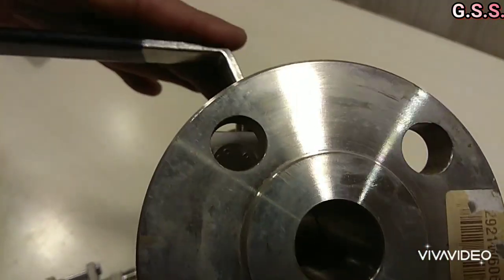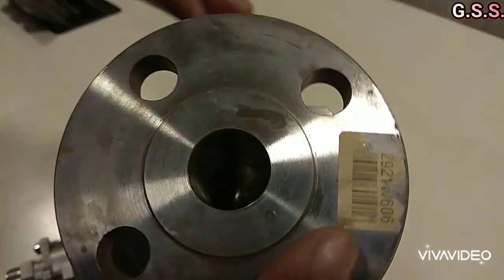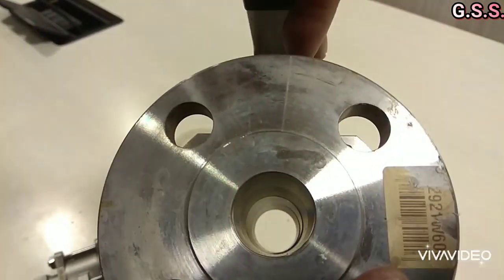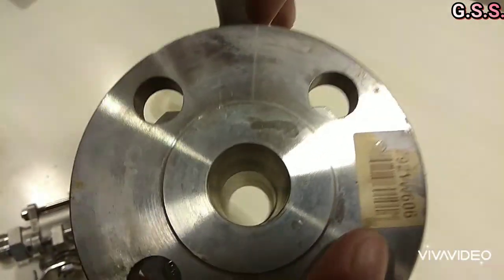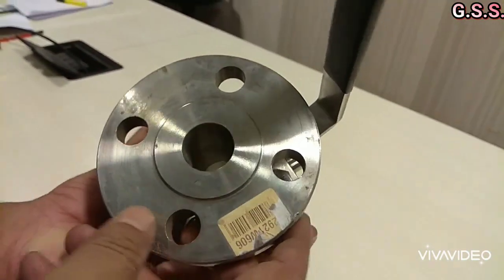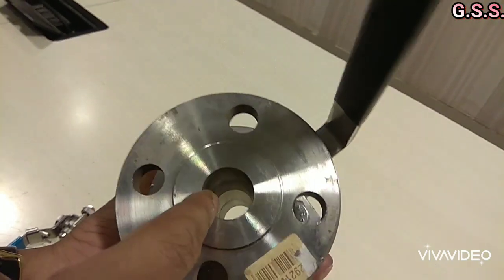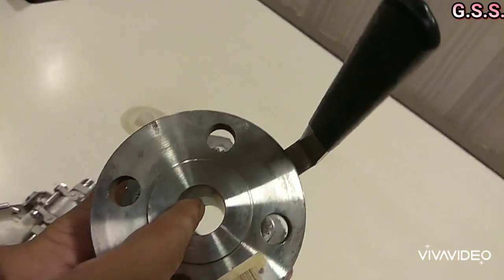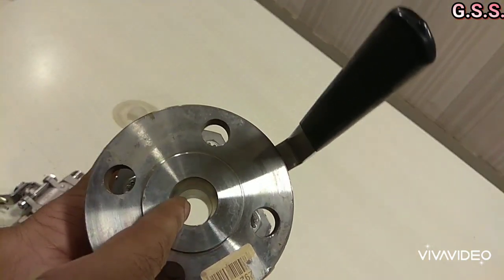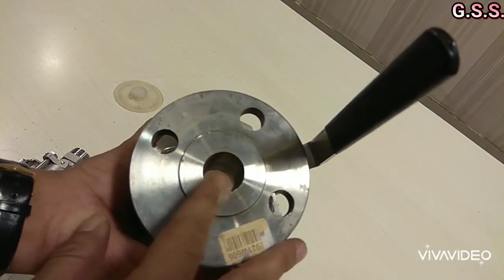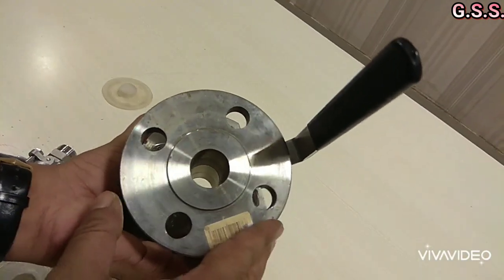I am closing it and again I am opening it. There is no obstruction. This is a full bore valve. Through this full bore valve, liquid or fluid can pass smoothly. Nothing will accumulate inside the valve, and pressure drop will also be less for this full bore valve.